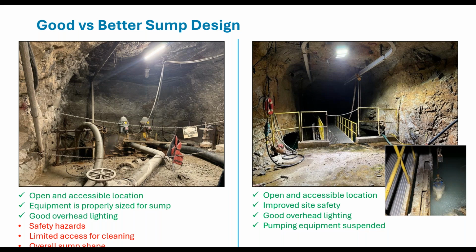While there are some positives about the sump design, including that it's in an open, accessible location. The equipment there is properly sized, featuring two 300 horsepower motors on vertical turbine pumps. There's good overhead lighting, right? We're underground, it's dark. We want to make sure that we have adequate lighting to enhance the safety for our personnel as much as possible.